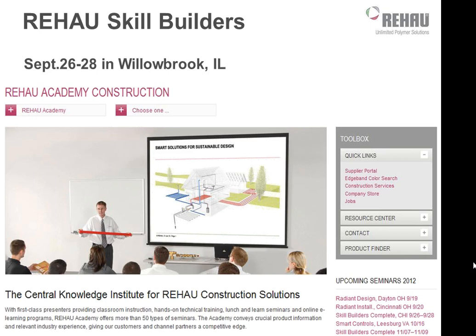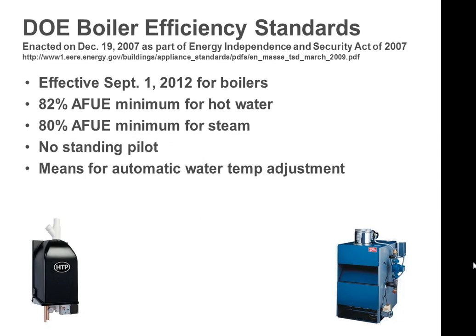Obviously, in a 45-minute webinar, we can't cover everything we'd like to. One of the things I want to point out on the hydronic side of the equation related to these systems is that the minimum boiler efficiency standards just changed a couple weeks ago. Technically they changed 5 years ago, but they just went live 3 weeks ago. Effective September 1st of this year, all boilers need to be 82% minimum AFUE. That's the least efficient boiler that you could get. If you have one in stock, or we have one in stock, you can still install it, but they can't be manufactured any less efficient than that going forward.